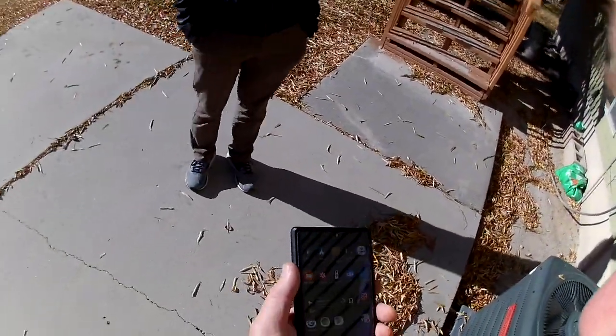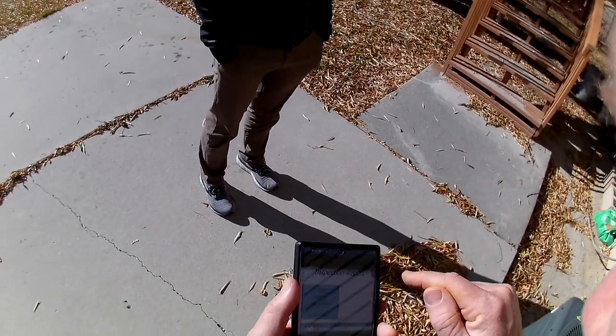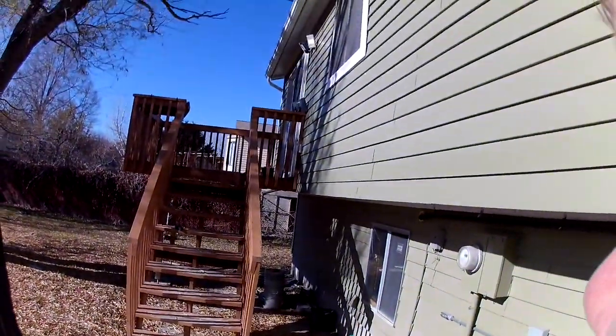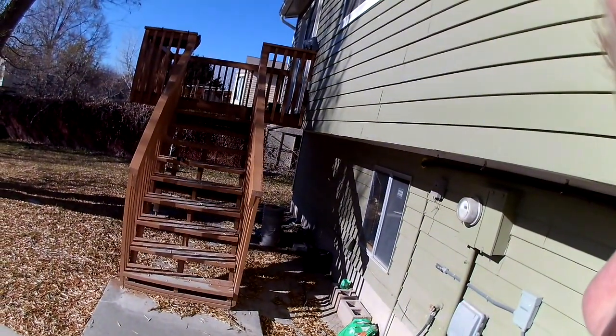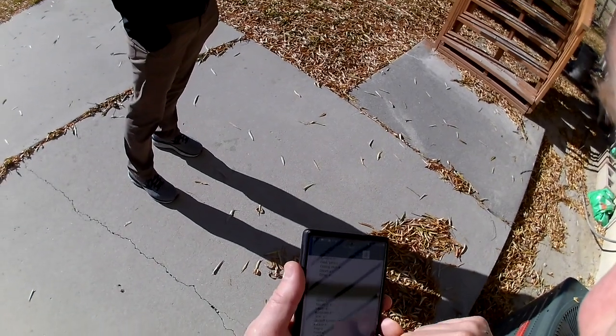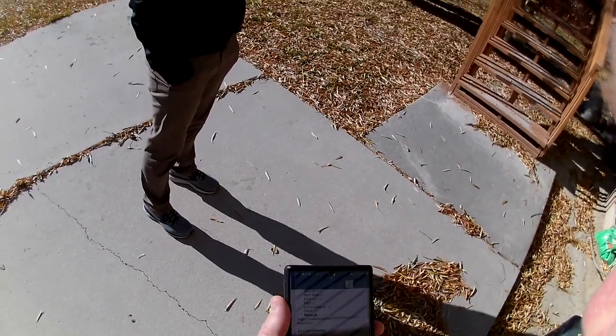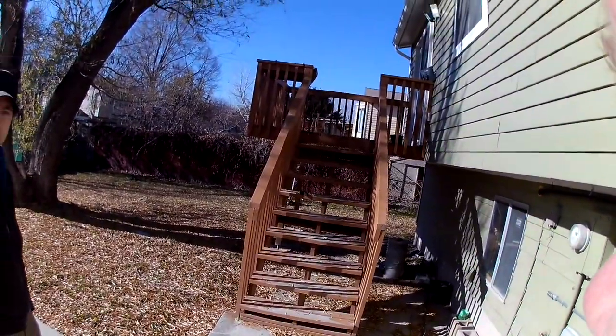So you've got a 2.5 ton unit there. You said that we had 1,700 square feet. Using rough home inspector math, now you've got basically a rambler with a basement here. Is that right? It's a split level. Okay. 2.5 tons, using rough home inspector math, is barely adequate. So you may be cursing a little in the summer.